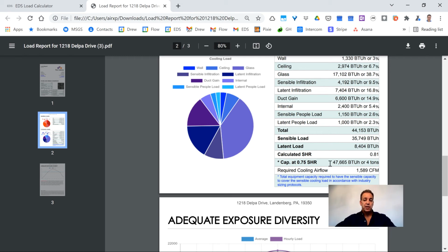While you're sizing, in this particular case, for 75 degrees, we may only get to 78 degrees, and then the customer's going to call you, and you're going to send a technician out. The technician's going to diagnose that you installed the system properly and that the system is working fine, it's just not keeping up. Then the sun's going to go down, the customer's going to be happy that night, but then they'll be complaining the next time it reaches above those design temperatures.